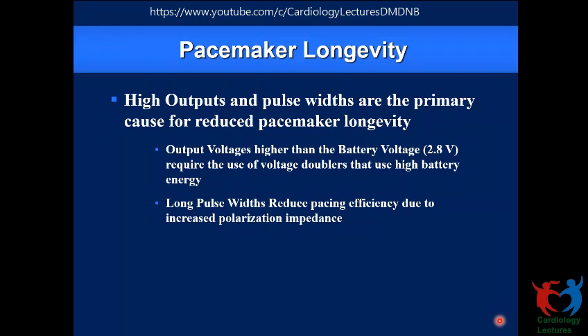And in a dependent patient, if it doesn't pace, then you might have a syncope on the pacemaker. So the norm is to find out the threshold during each programming and then program the output at twice the threshold. That's kind of a chronaxy. That twice is the margin, a safety margin to make sure that even if the threshold varies a little bit, it doesn't matter, and patient safety is not compromised.